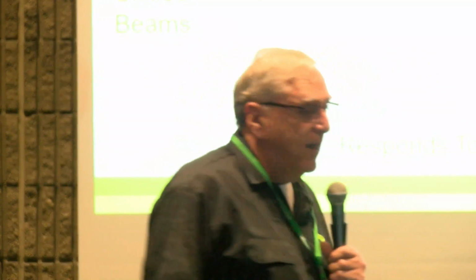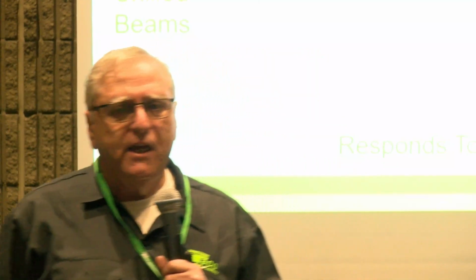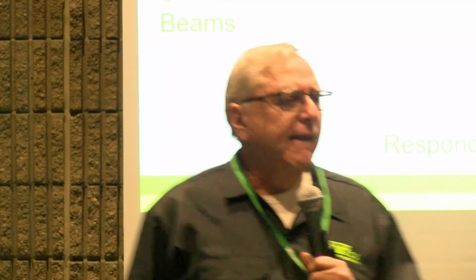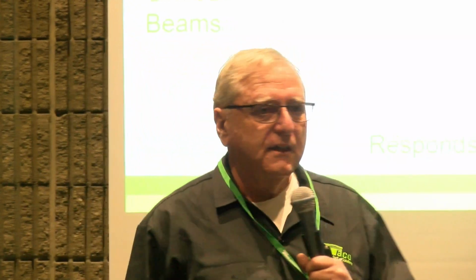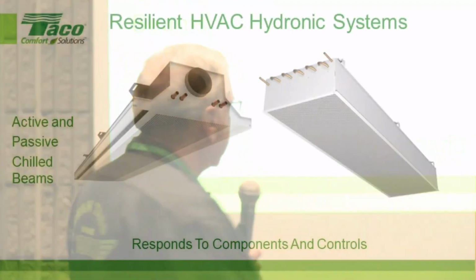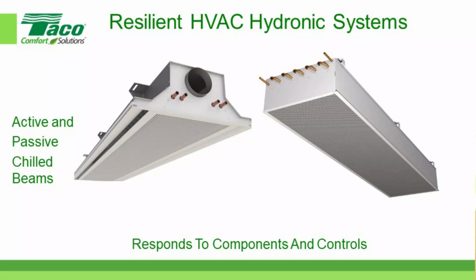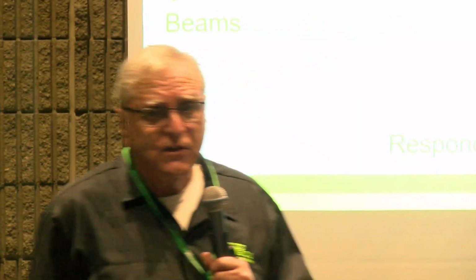The major advantage to active chill beams is that they're substantially less energy consuming than conventional systems like VAV systems. They use about one-fifth as much air as an all-air variable air volume system uses. And so you get rid of the sensible heat in a space by circulating water through the tubes. Let's see if I can point to it here. Through the tubes above the dew point temperature. An active chill beam uses air to induce room air across the coil that's inside here. And a passive chill beam is basically just a cooling coil inside a box, and if we circulate chilled water above the dew point temperature, it'll remove sensible heat. So they're a huge energy saver. So this is another technology that hydronics does extremely well.